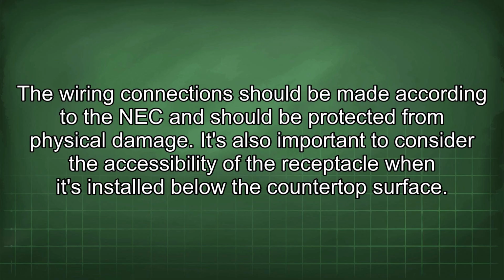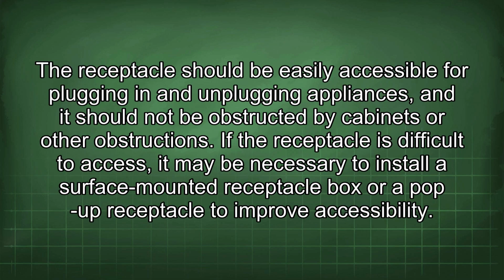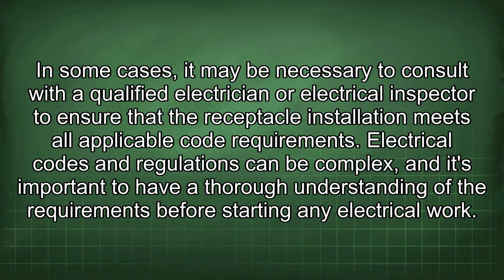It's also important to consider the accessibility of the receptacle when it's installed below the countertop surface. The receptacle should be easily accessible for plugging in and unplugging appliances, and it should not be obstructed by cabinets or other obstructions. If the receptacle is difficult to access, it may be necessary to install a surface-mounted receptacle box or a pop-up receptacle to improve accessibility. In some cases, it may be necessary to consult with a qualified electrician or electrical inspector to ensure that the receptacle installation meets all applicable code requirements.